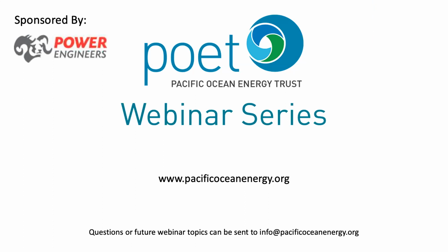First of all, Steve, why would the long distance transport cable need to be in shallow, less than 100 meters of water? It doesn't. What we've got is we have to get the end terminations in the dry, and make sure the cable itself is not in dynamic mode, so it's secured in a way that it doesn't flop around all over the place. When we talked about this over the last few weeks, we were saying, well, why not put a fixed platform in about 100 meters? Because we know that's doable. But really, these fixed platforms can go out a lot further should the need arise.